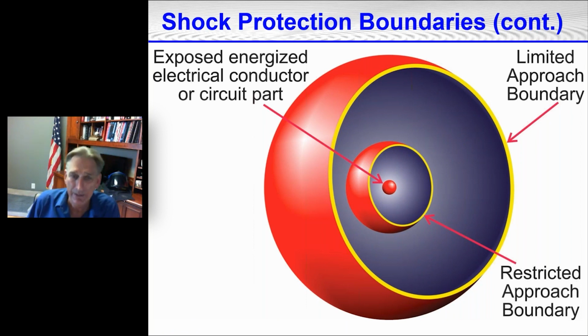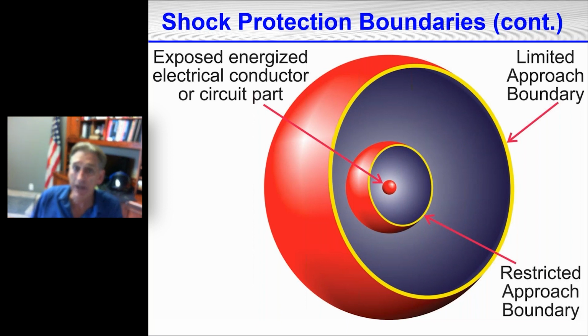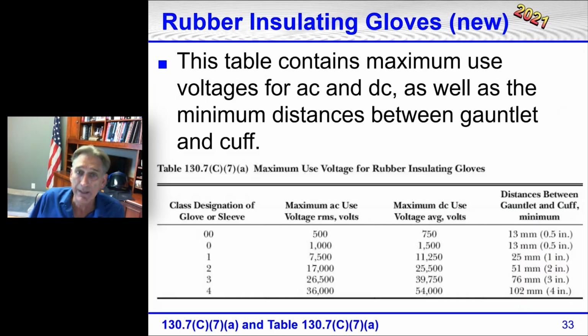Here's a drawing that I made representing the live conductor or circuit part in the middle. The closest boundary is the restricted approach boundary, then we have the limited approach boundary. There are certain things that we have to do or not do at each of the boundaries before crossing them. This is a new table that was added to the 2021 edition of 70E. It contains maximum use voltages for AC and DC, as well as the minimum distances between the end of the rubber and the end of the leather. There has to be at least a minimum distance so that you're not going to have an arc over.